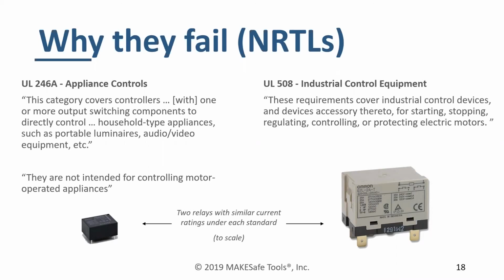Now, Doug mentions that this G7L relay has a lot of features built into it as part of that motor requirement, which makes it able to extinguish those arcs. Part of it is that it actually has double contact—instead of one piece of metal separating, there's two, so it shares the load. It also has different ways the arc can travel that make it go away from the contacts faster. Lots of things built into this, not too different from a circuit breaker, make it safer for motors.